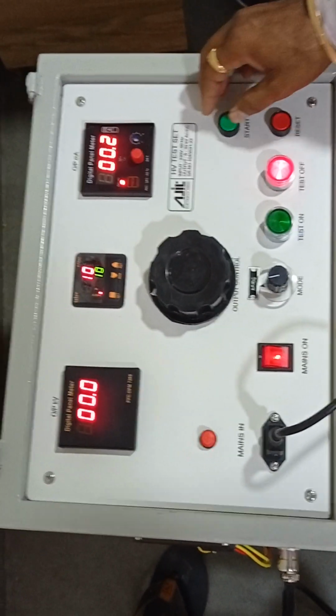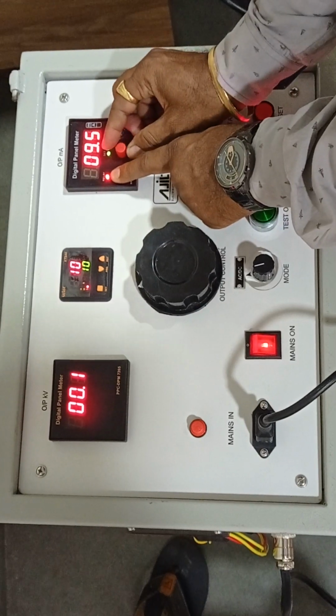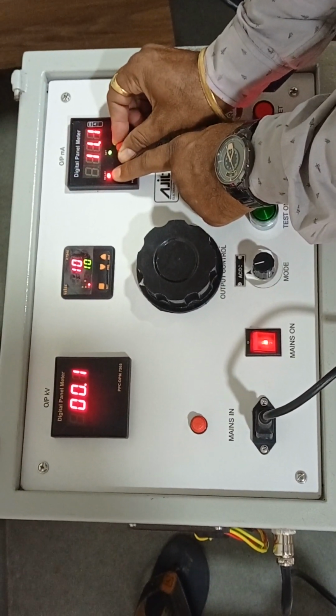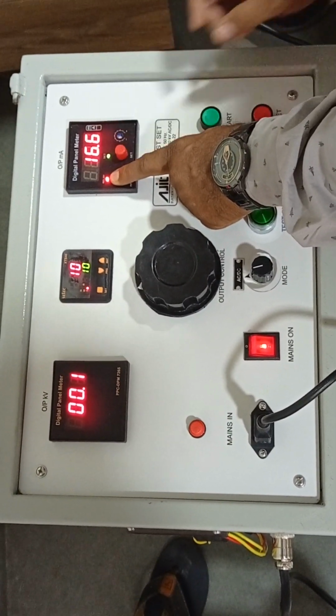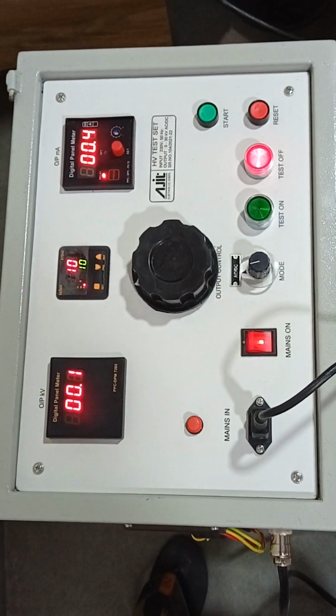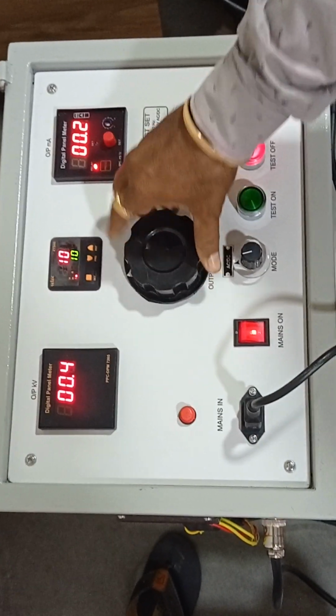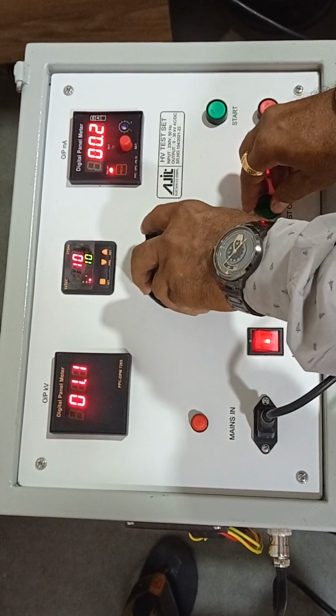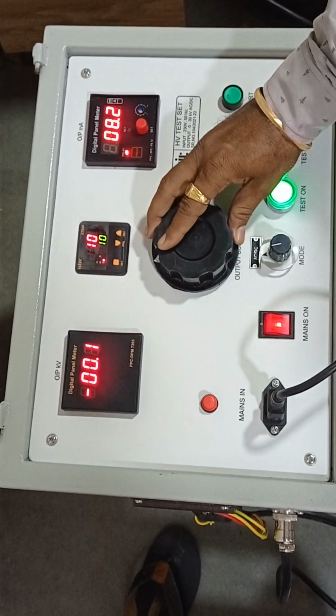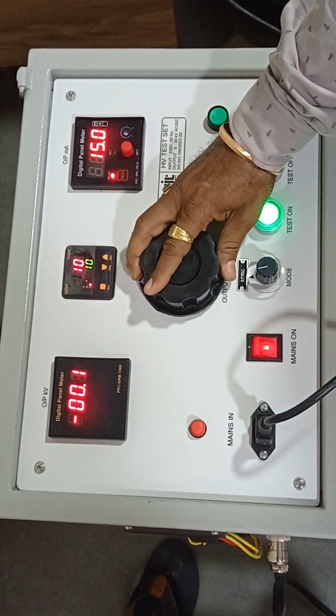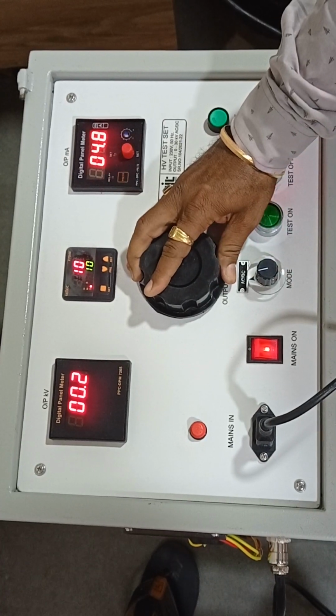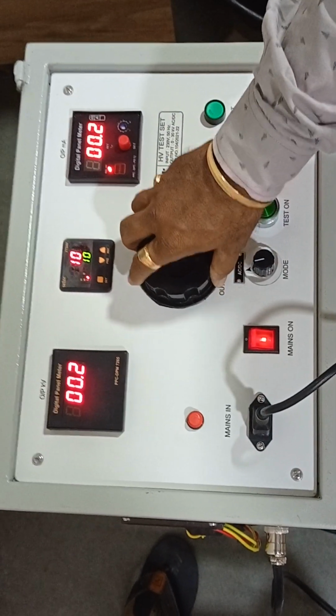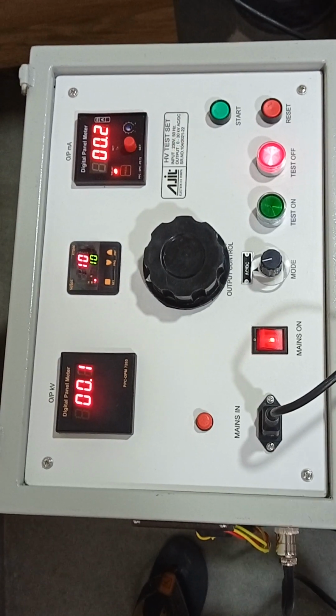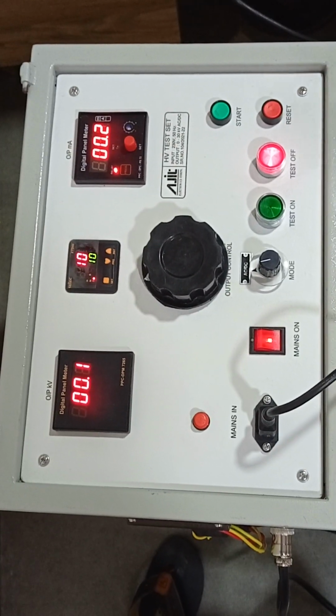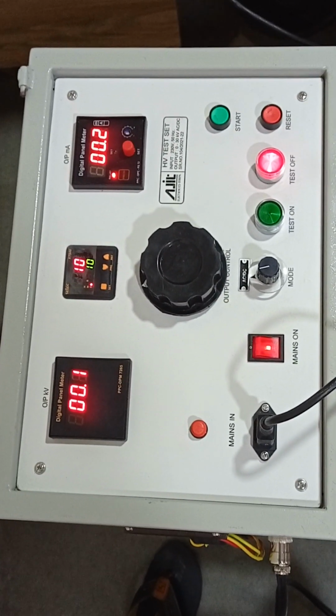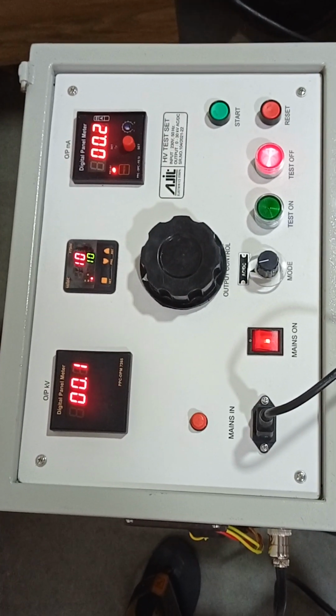This way we can change this value. Suppose I keep it somewhere around 16.6, again I bring this knob to 0 and start. Now we can go gradually, and once it crosses the set limit, the output will be tripped off. This is the way we can check the self test of the instrument and verify the instrument is working properly.